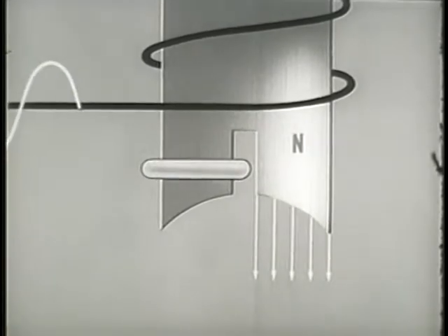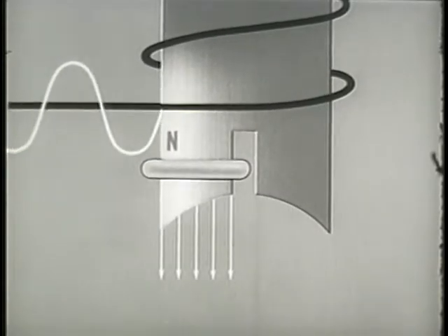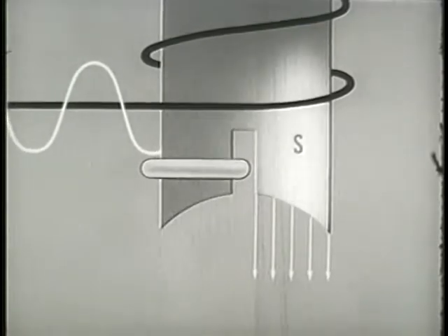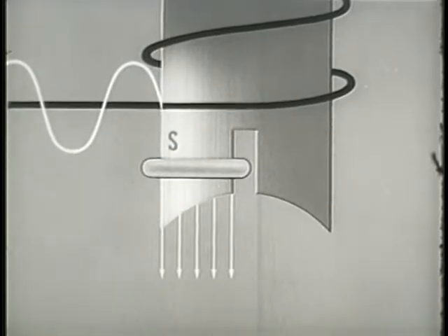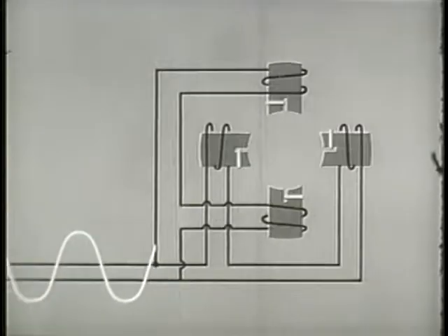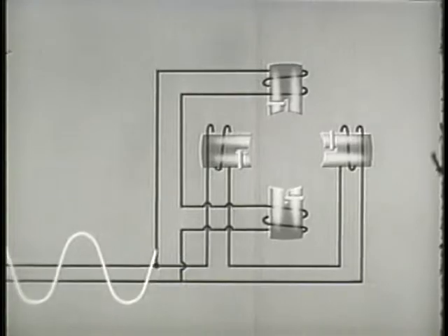Lines of force will emerge from this unshaded section of a pole face first. The inductance caused by the ring makes the shaded portion of the pole lag behind. This alternating pulsating action creates a phase difference within the pole. Let us see now how the use of shaded poles actually produce a torque or turning force in a single-phase induction motor. The single-phase AC energizes the unshaded portions of the poles first and creates magnetic fields in these areas.